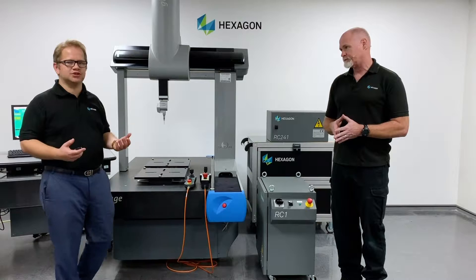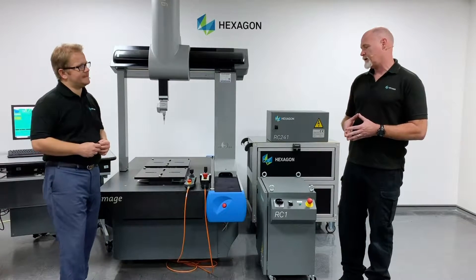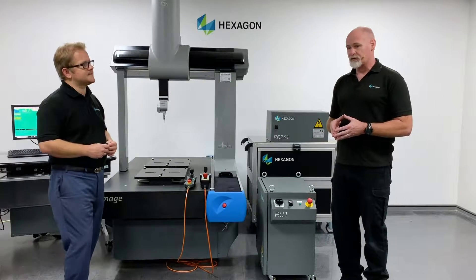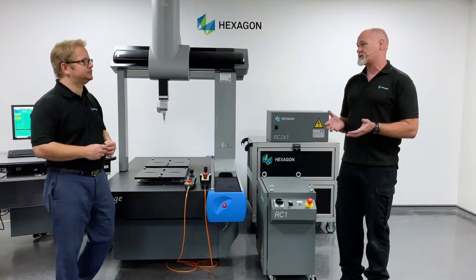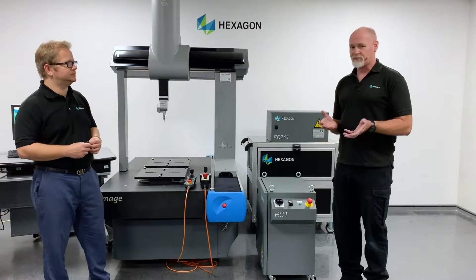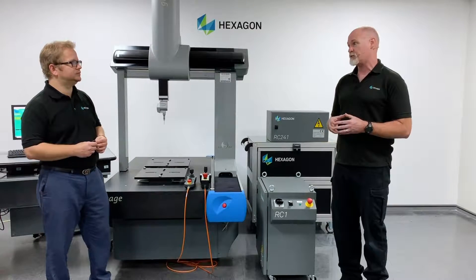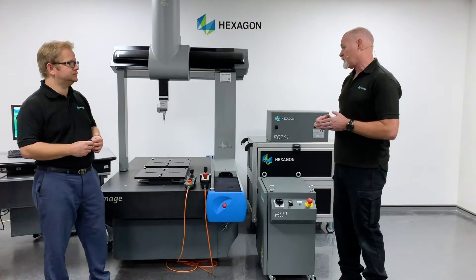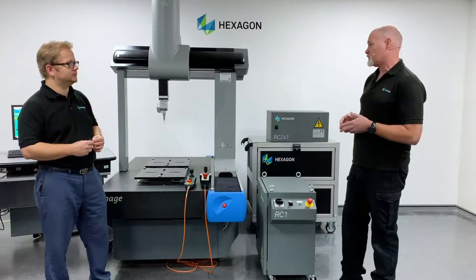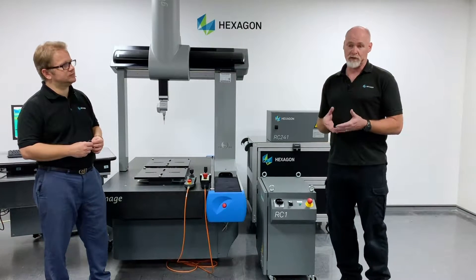And if I'm a customer, why would I need to do this? Certainly from a customer care perspective, Hexagon have quite a lot of CMMs out there with relatively old controllers. A lot of those controllers now have what we would consider to be obsolete electronic components inside them. As a consequence, it's almost impossible to find spare parts for them, which from a customer's perspective could be quite bad from a productivity point of view. So we're offering an opportunity for them to consider that risk and upgrade or retrofit their machine to our current line of controller, to safeguard themselves for many years to come.